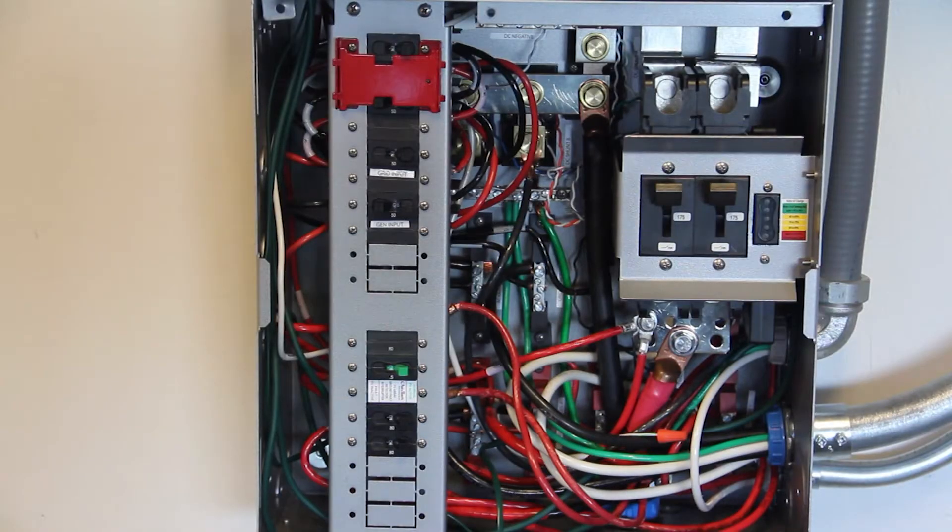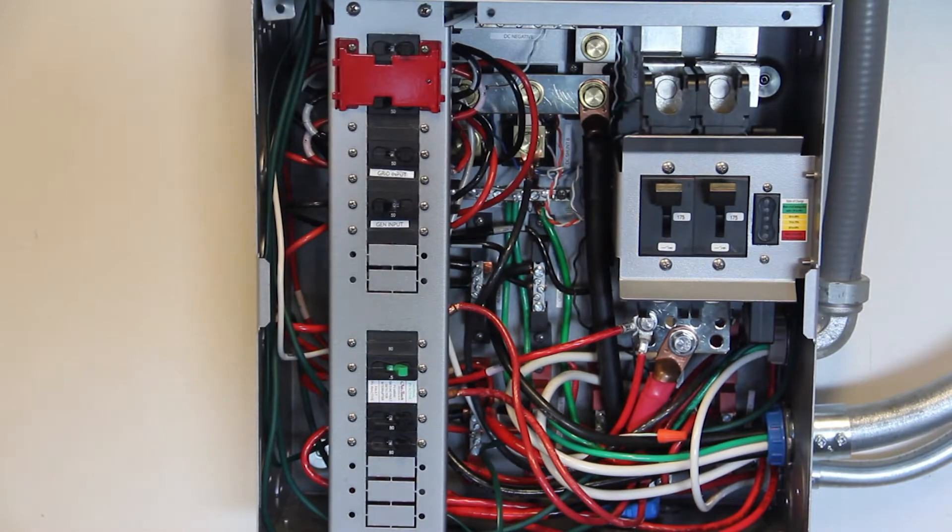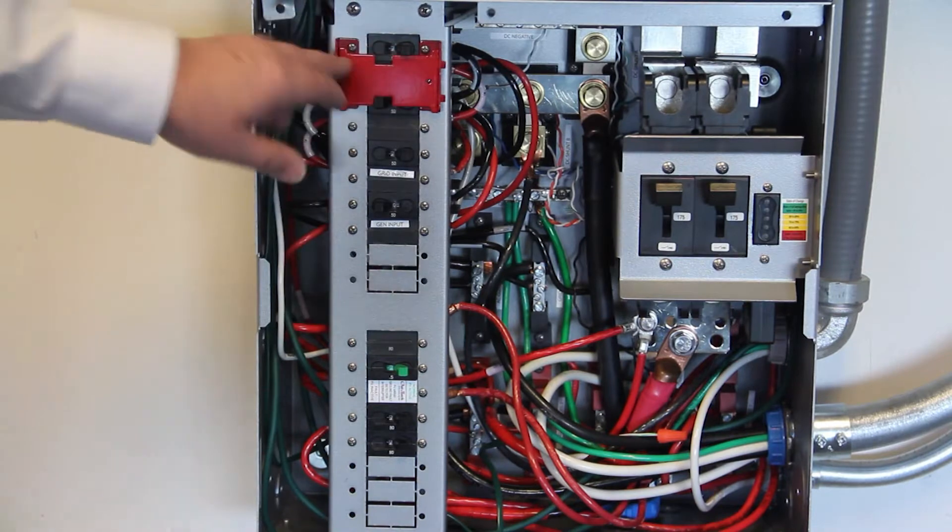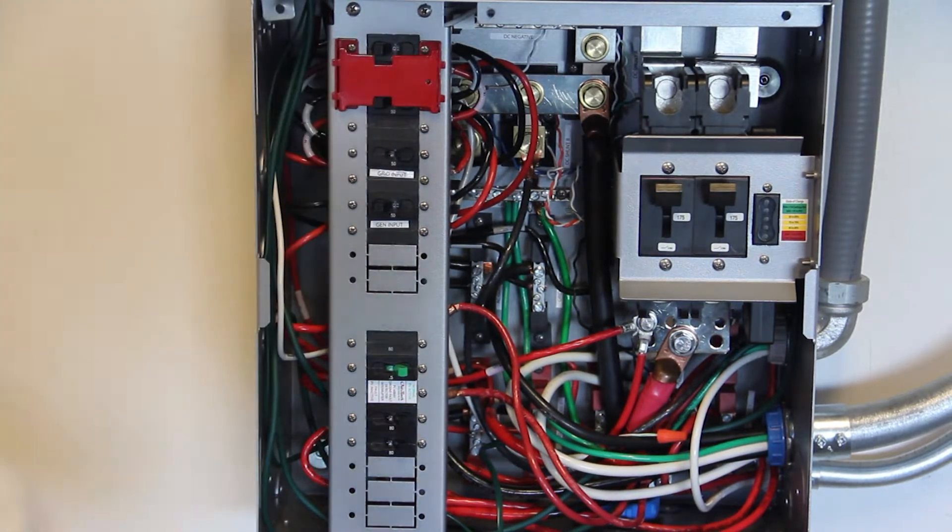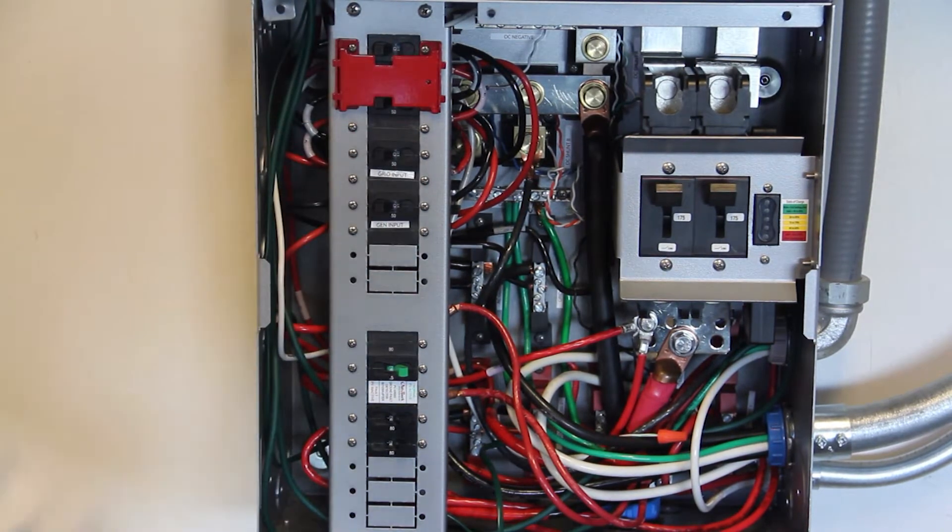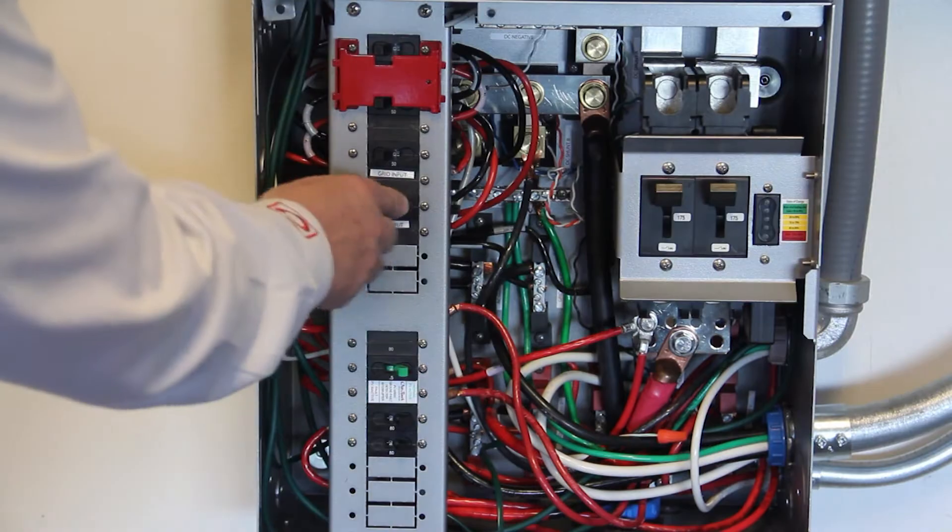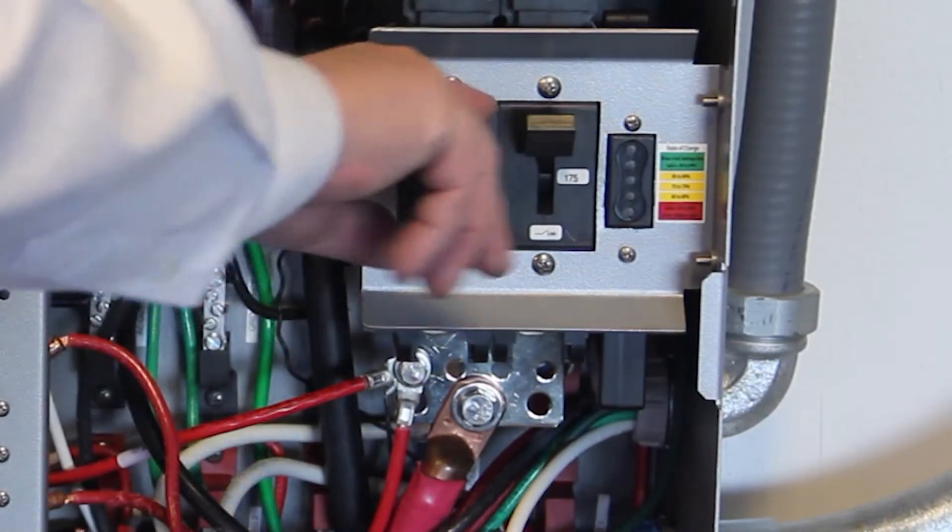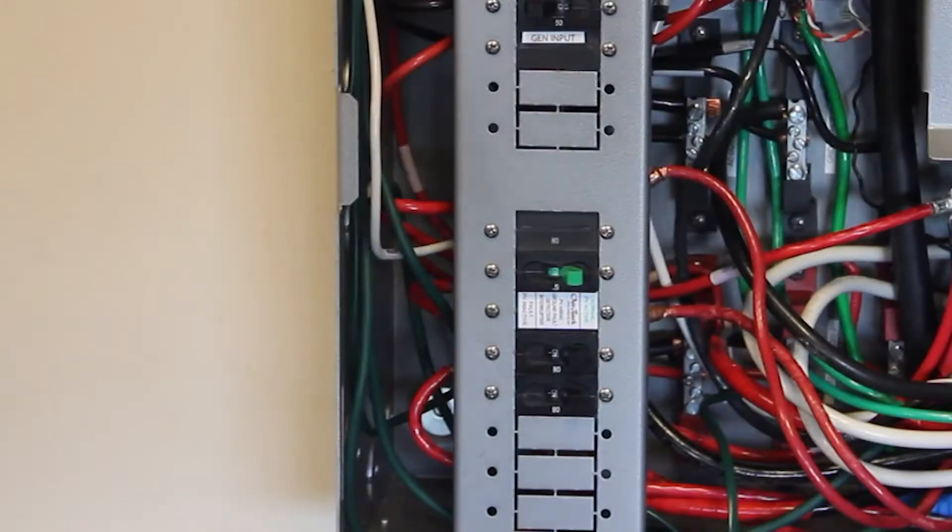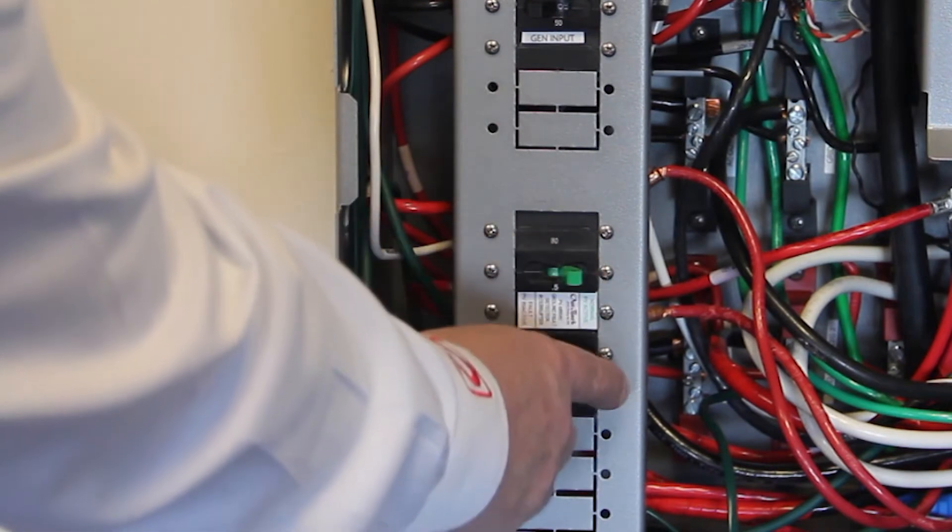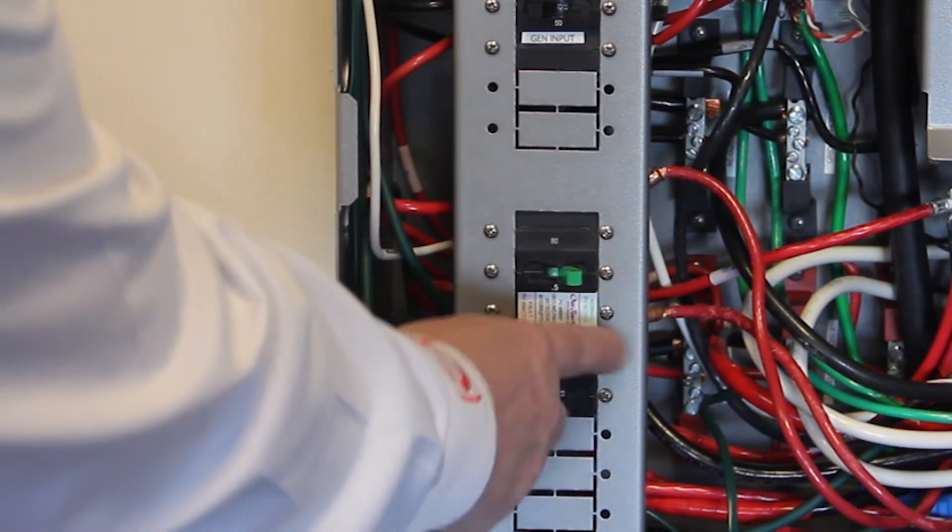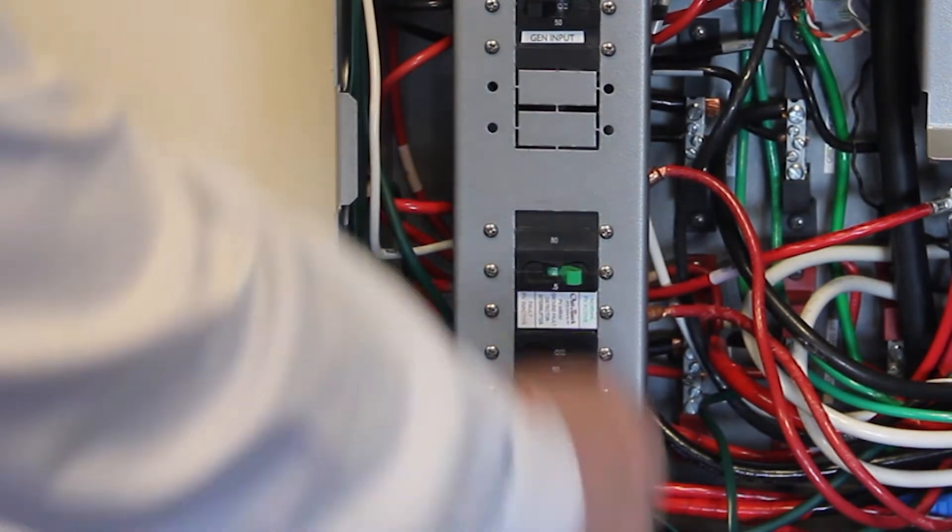Turn off the following breakers in this order: AC out breaker, grid AC input breaker, generator AC input breaker, main DC breakers, PV input and charge controller output or GFDI.